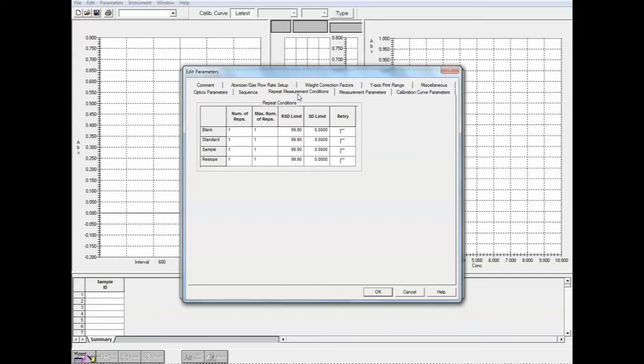Under repeat measurement conditions, this is where we're telling it what we want it to do when it takes a measurement. It gives a number of repetitions for each sample that we're going to analyze. So if we do a blank, if we do standards, if we do a sample, that's generally what we're doing in this lab. What we're going to do is change each of those to 3. We want the machine to take 3 measurements for each solution that we test. You'll see what I mean by 3 measurements when we get into actually doing the analysis.